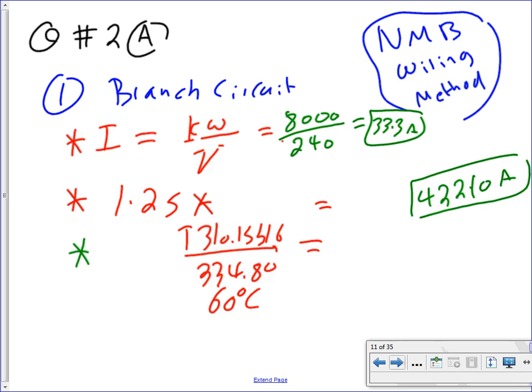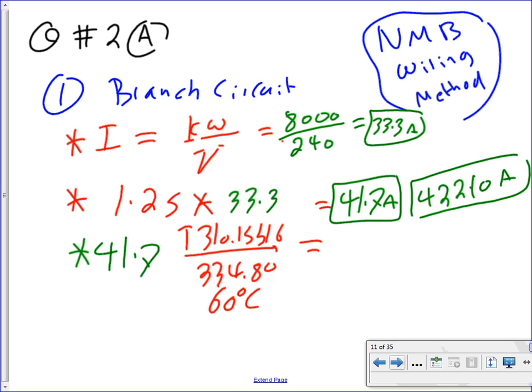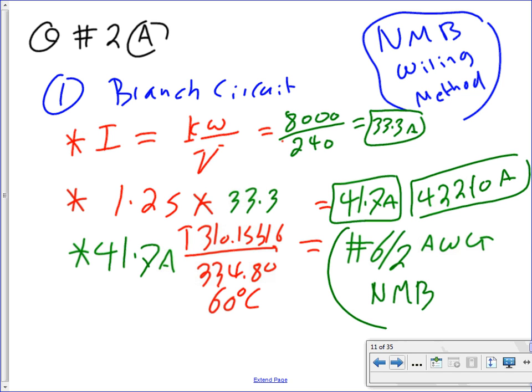When you size your conductor, it's a continuous load, 422.10(A) is your reference. So you multiply 1.25 by 33.3. You get yourself a 41.7 amp. And you go to 41.7 amps, go to 310.15(B)(16), 334.80, 60-degree column, and that will get you a healthy number 6-2 AWG NMB cable. Very clear, no gimmicks, nothing.